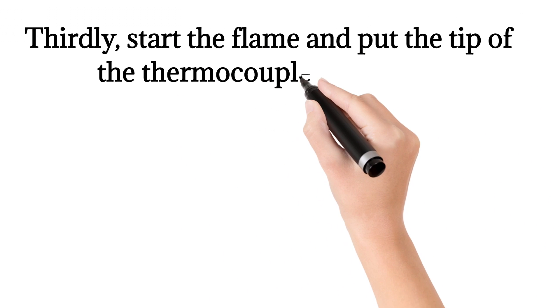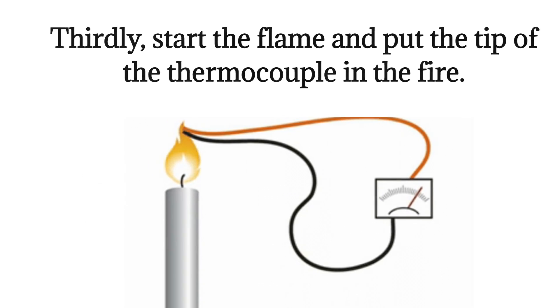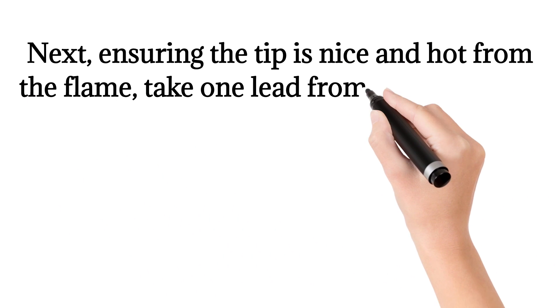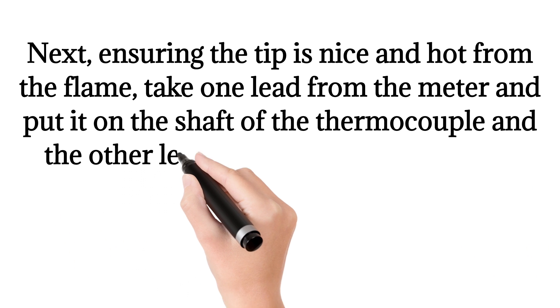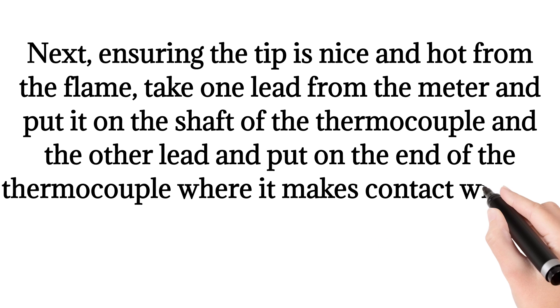Thirdly, start the flame and put the tip of the thermocouple in the fire. Ensuring the tip is nice and hot from the flame, take one lead from the meter and put it on the shaft of the thermocouple. Put the other lead on the end of the thermocouple where it makes contact with the gas valve.